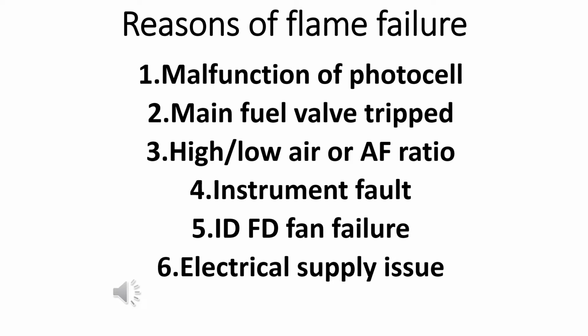Instrument fault means if your level transmitter is faulty, if your steam flow transmitter is faulty, if there is any faulty instrument, then it will trip the boiler, which ultimately sends a signal to the burner management system and will cause the flame failure. Number five is the ID and FD fan failure.